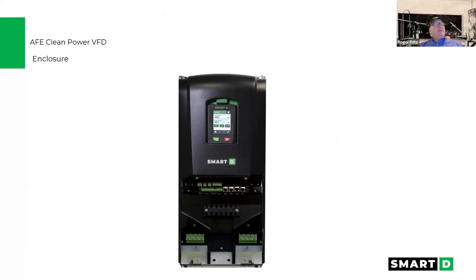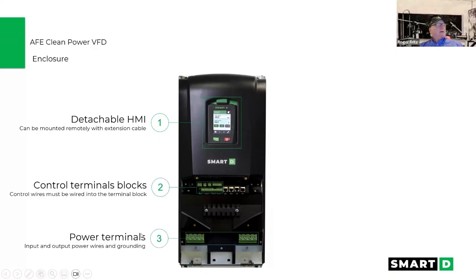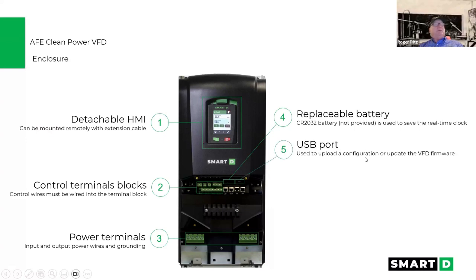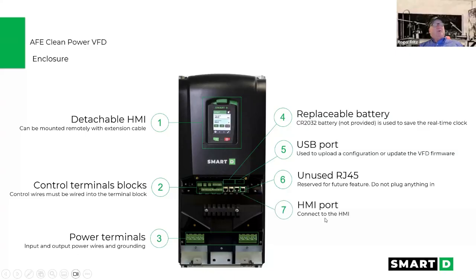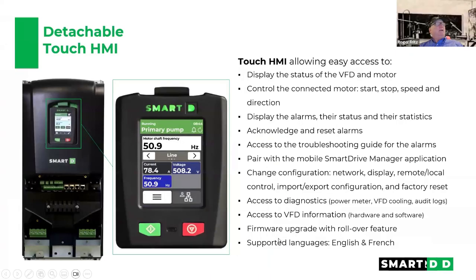The drives are built very simply, have a lot of IO input. They have the HMI built in, it's detachable, so you can mount it remotely if you need. The terminal blocks, the power terminals are here just in and out. It does have a replaceable battery for the real-time clock inside. It's got USB ports, so you can talk to it directly through a USB cable and the firmware. It's also got an unused RJ45 there. And then it's got an HMI port, so you can remote mount it. And then it's also got a full Ethernet port to go to a gateway.